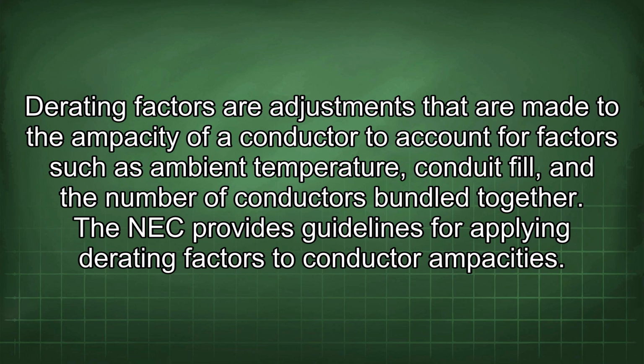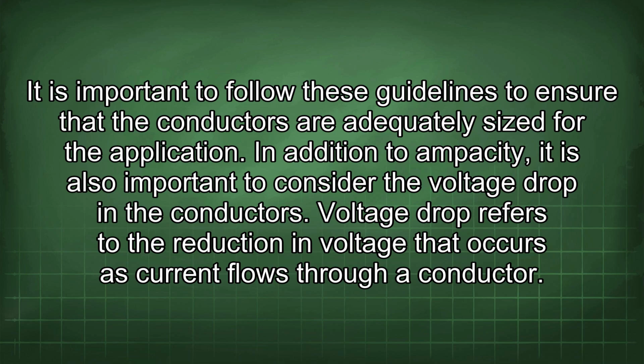Derating factors are adjustments that are made to the ampacity of a conductor to account for factors such as ambient temperature, conduit fill, and the number of conductors bundled together. The NEC provides guidelines for applying derating factors to conductor ampacities. It is important to follow these guidelines to ensure that the conductors are adequately sized for the application.